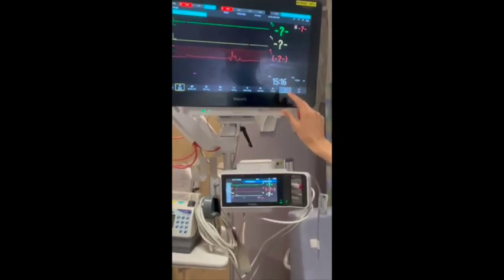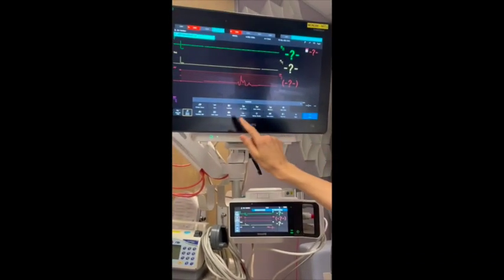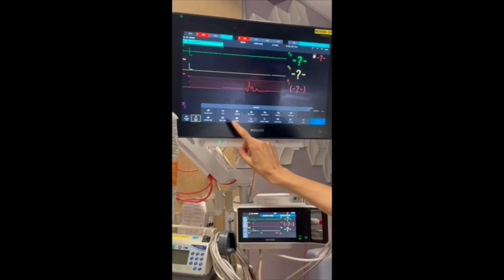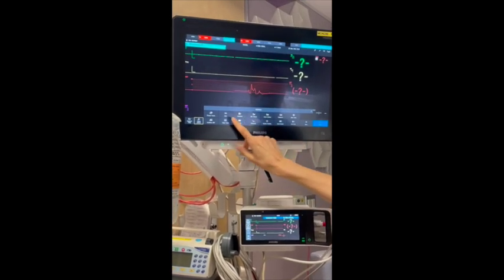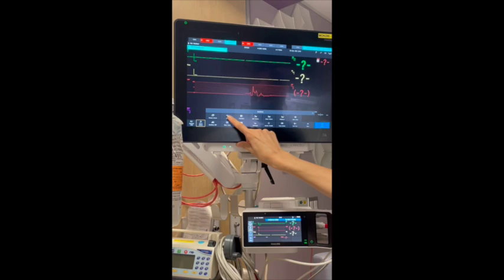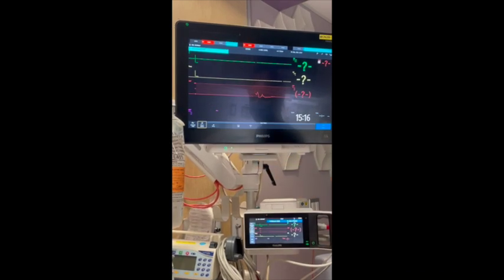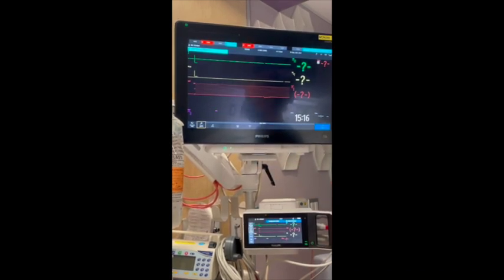Depress the key labeled 0 on the blood pressure module until a tone is emitted, and you see a 0 on the monitor screen. The 0 and calibration process is complete when the monitor states that the line has been calibrated.